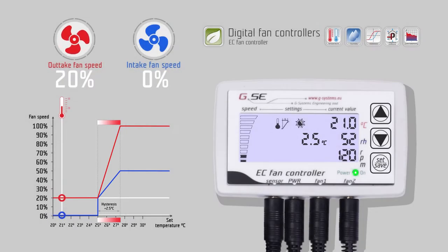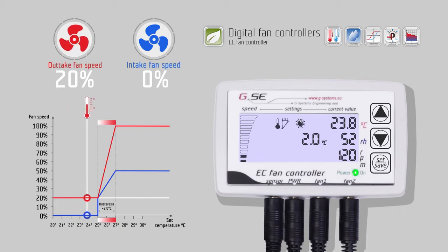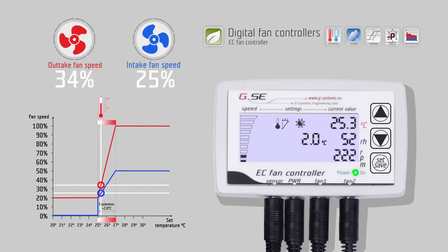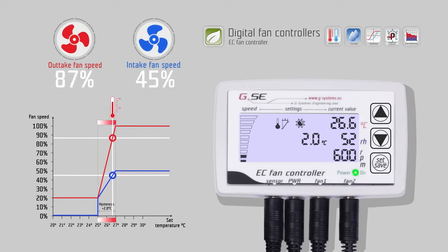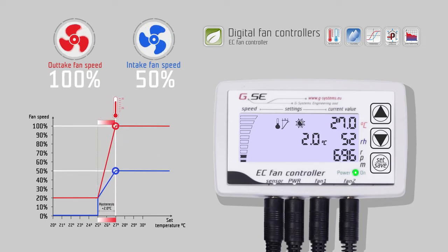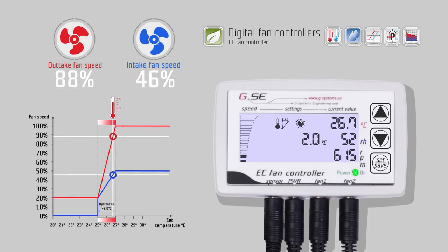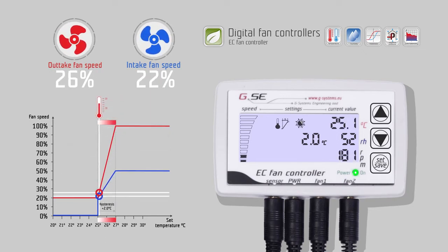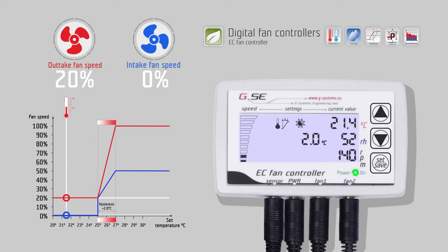The hysteresis refers to the value between the lowest and the highest value of the regulation. For example, we set the hysteresis to 2 degrees Celsius and the day temperature to 25 degrees Celsius. The fan will start at 25 degrees room temperature, and reach maximum speed at 27. In these 2 degrees Celsius, the fan speed will change linearly, according to the measured temperature.